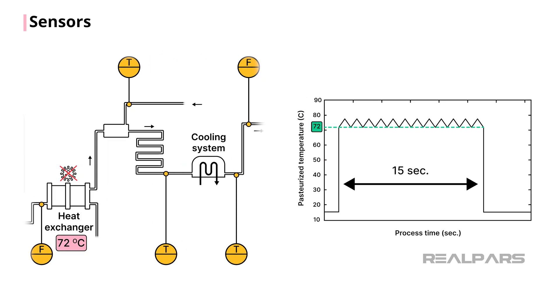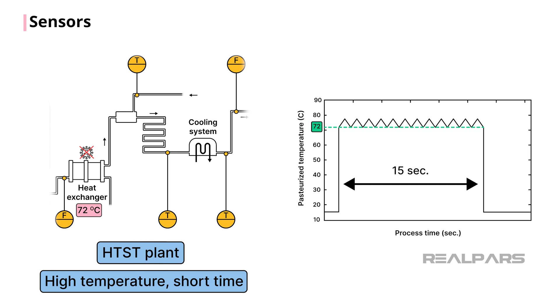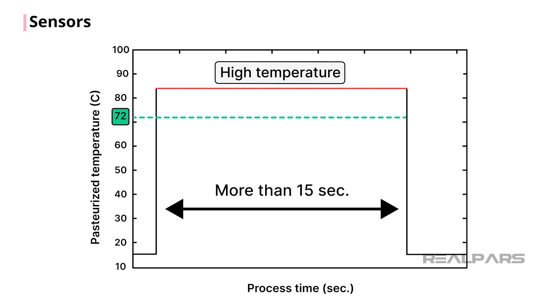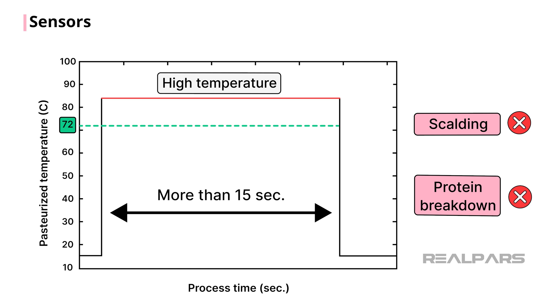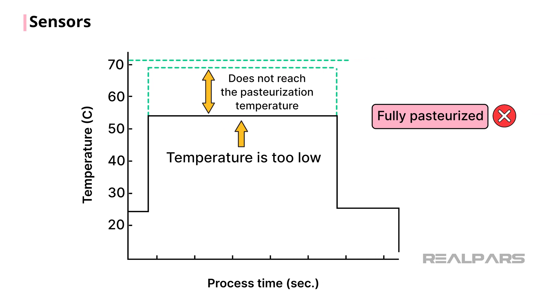A common way to reach these parameters is to flow the raw milk through an HTST, a high temperature short-time heat exchanger. The exchanger is heated to 72 degrees Celsius and is sized so that the milk at the intended flow rate has a residence time of exactly 15 seconds. If the temperature is too high, or if the milk remains at an elevated temperature for too long, scalding or protein breakdown may occur. If the temperature is too low, or if the milk does not reach the pasteurization temperature, the milk may not be fully pasteurized.